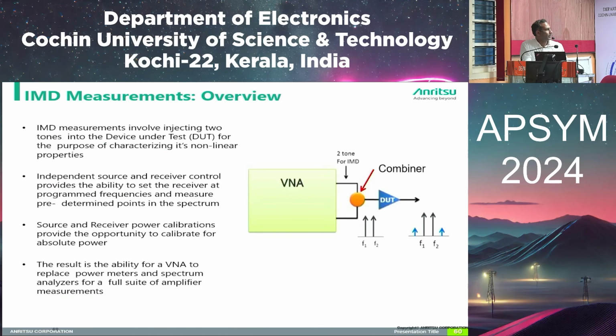So this is the VNA. When you come to non-linear measurements, we can do the IMD measurements. Usually for the IMD measurements, we will generate two tones. You will feed them to the input of the amplifier and measure at the output. Depending on the characteristics of a DUT, any amplifier or anything, it will create some harmonics also. So we will check at the output the level of the harmonics with respect to the fundamental. As we know, this should not be much, it should not be equal to the fundamental whenever it is created.